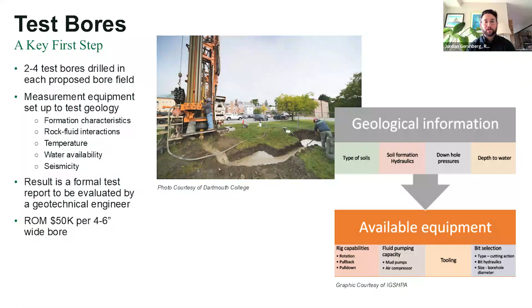Here's a couple of pictures just showing how much disruption can really be caused. These boreholes can be 500 to 1,000 feet deep, 4 or 6 inch wide holes. To connect all the various bores across a field together, they have headers called laterals that connect them, usually in a reverse return arrangement. That's something your geoengineer or whoever is designing the bore system can handle, and they all get combined. The combination is a whole separate system involving pumping capacities, temperature monitoring, and so on. But the idea is it's a closed loop: you're sending water out to exchange or absorb heat, and bringing it back.